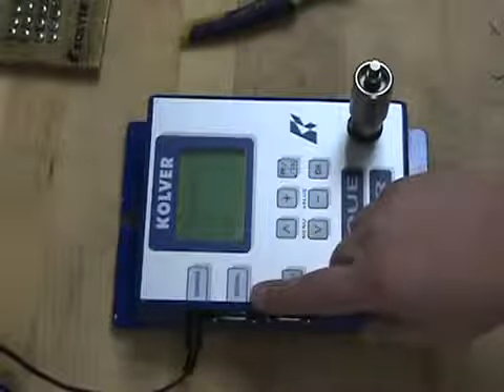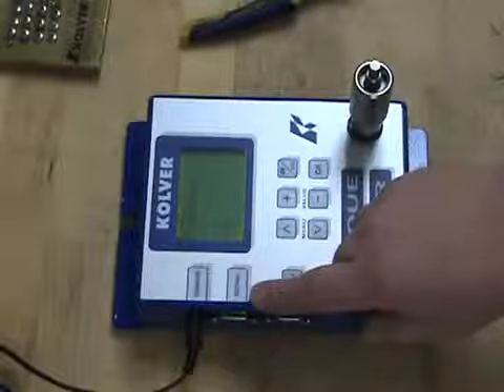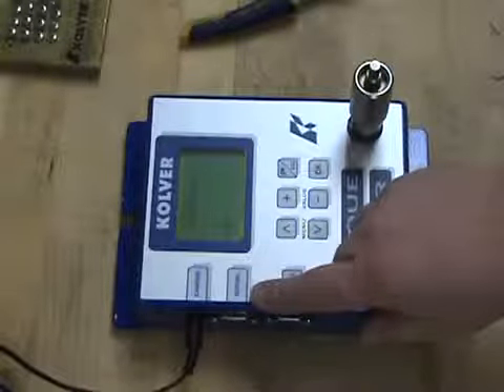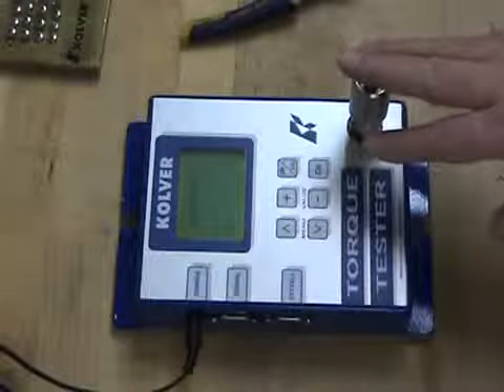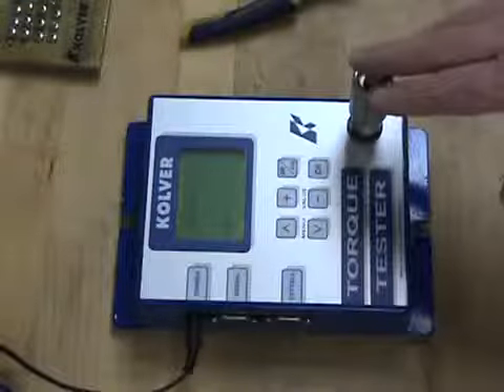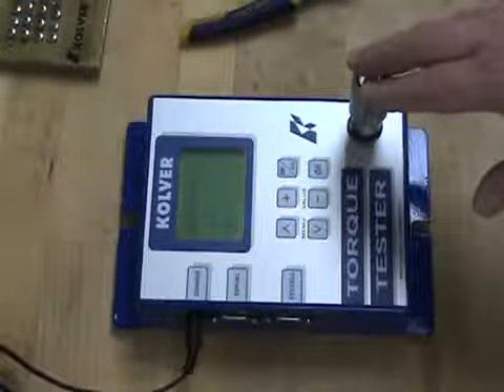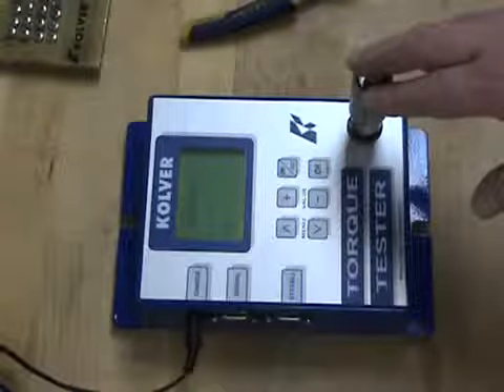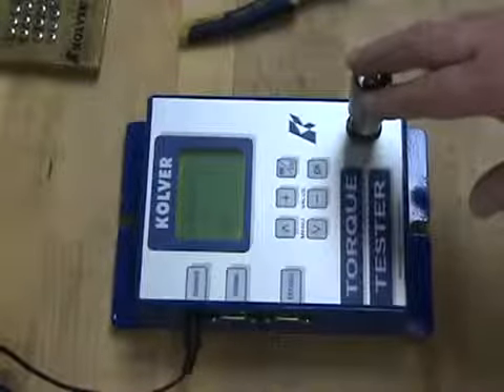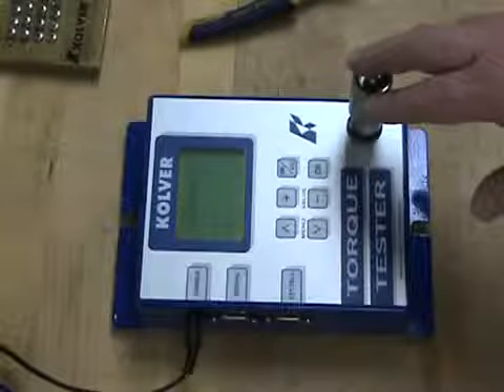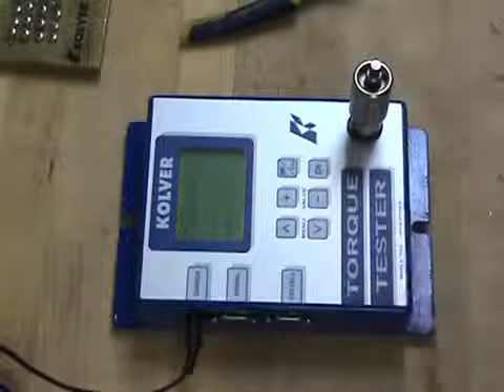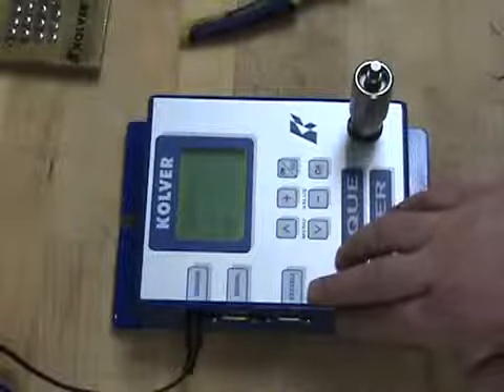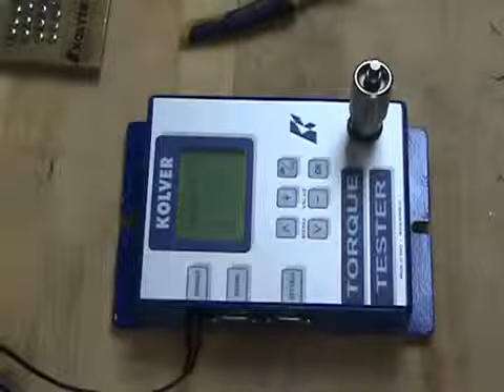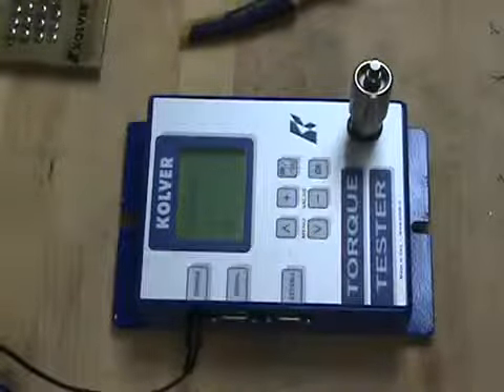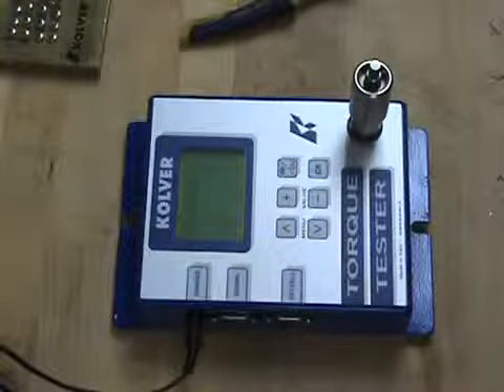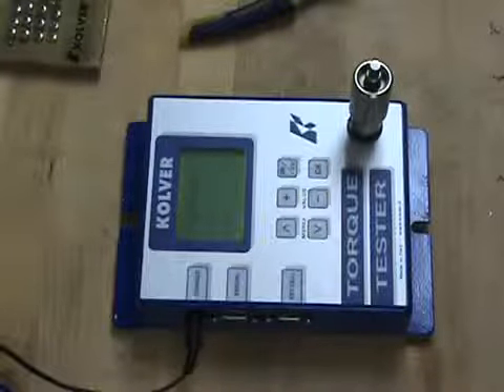The serial port, it is a standard serial port, and each time a rundown is performed on the analyzer, it will send a string of text data to a computer of your choice via the serial port, and you can capture that with a program such as Hyperterminal. The next one is the external cell. We do have rotary transducers that can be plugged into this unit, and you can perform inline testing with that particular setup.